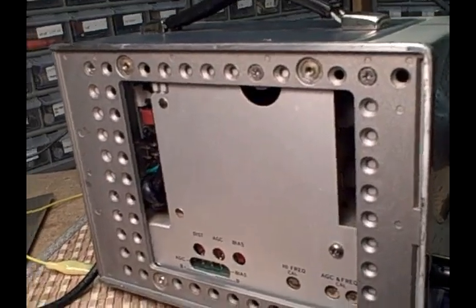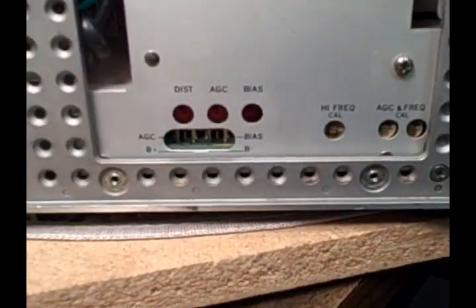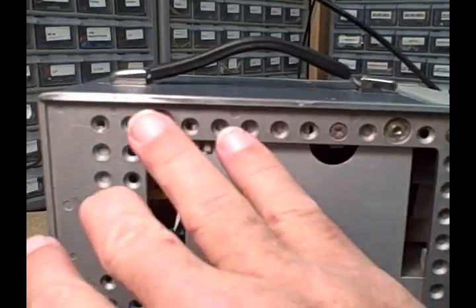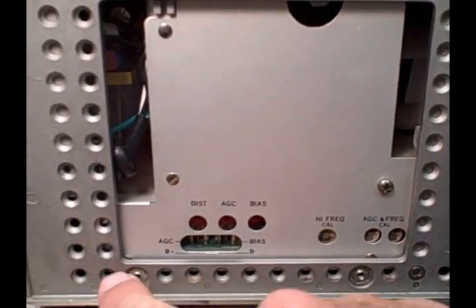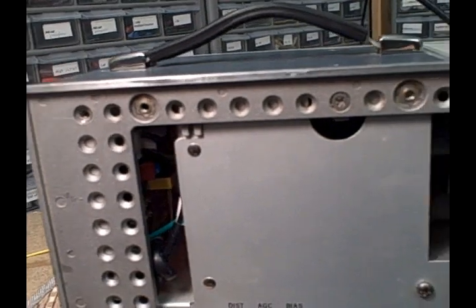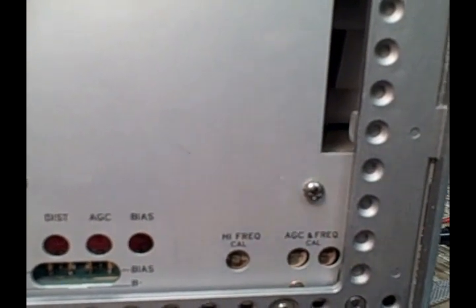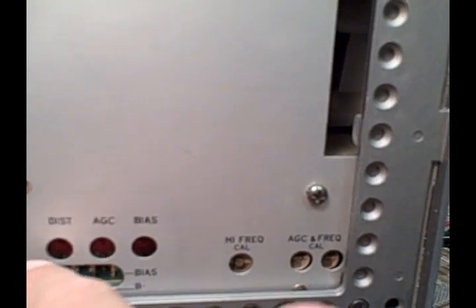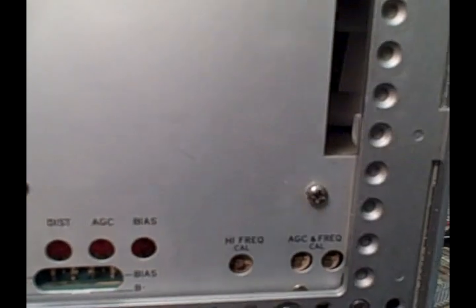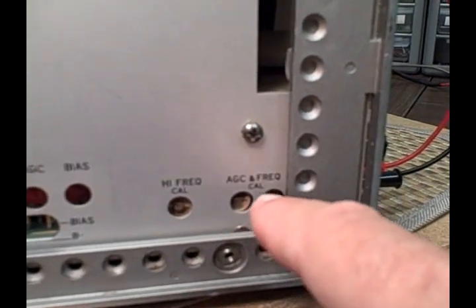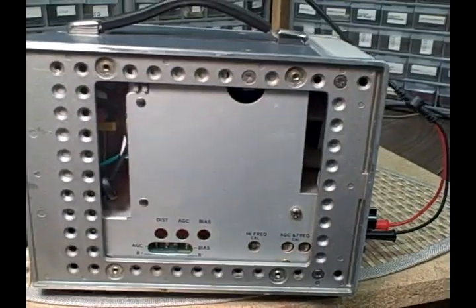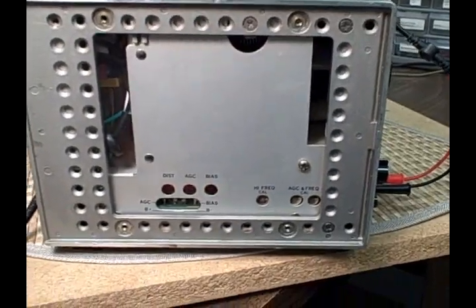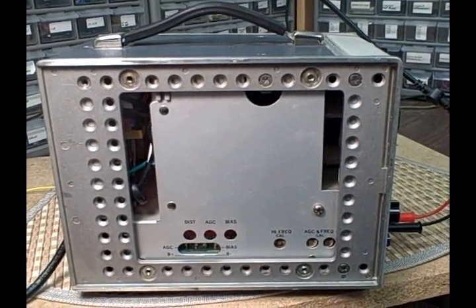Now with the side panel removed, we take a look at the outside here. Just take these four screws out, the blue-gray side panel comes off, and you have all your calibration points for the frequency and the automatic gain control line. Bias, your measuring points are in here: AGC, V plus, V minus, the bias measuring point, and adjustments for that, and adjustments for AGC and frequency calibration to the front dial. So we just went through all of that and we're going to go ahead and run a test now to see how we perform.